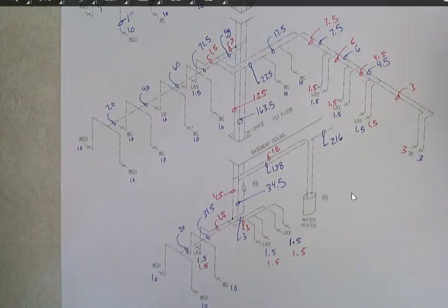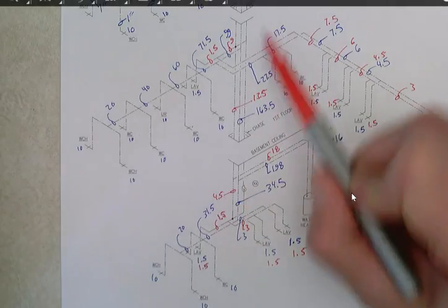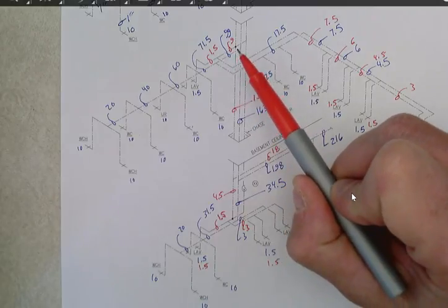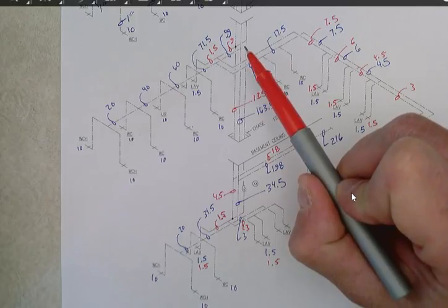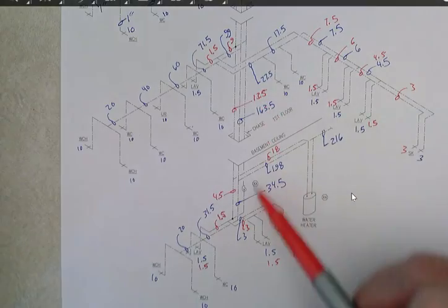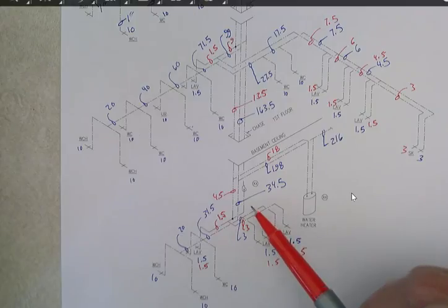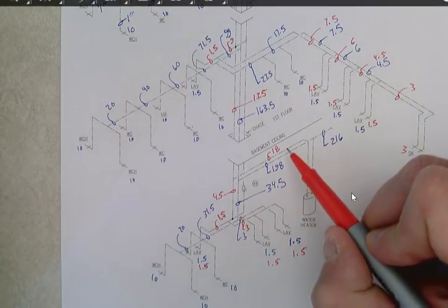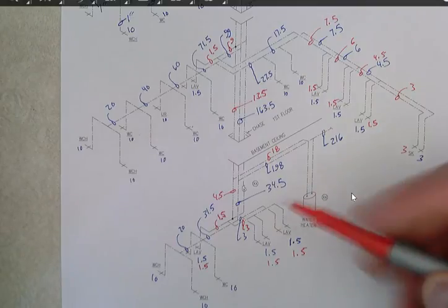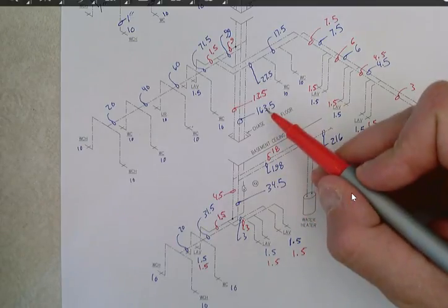The next step, I really went through and I paused the video and went through and added all of the fixture units for both the cold water and the hot water for the basement floor and the first floor. And one of the significant things about this is whenever you look at the hot water system, it really doesn't have many fixture units. You can see 1.5 on the one side, 7.5 on the other side from a sink and 3 lavatories, because we're not supplying anything to the water closets or urinals, so I ended up with 9, 13.5. One of the big things that I want to make note of is I only ended up with 18 total for the hot water.